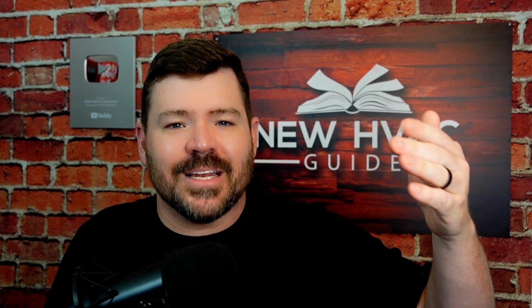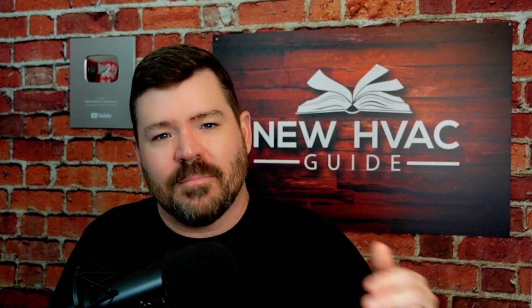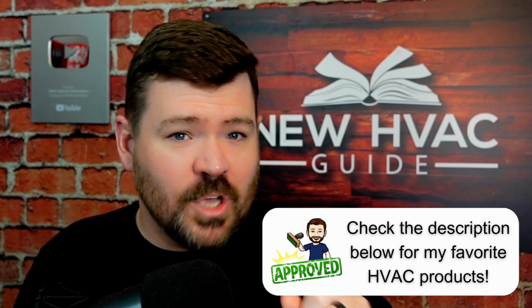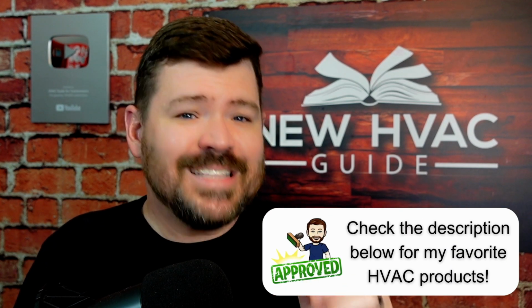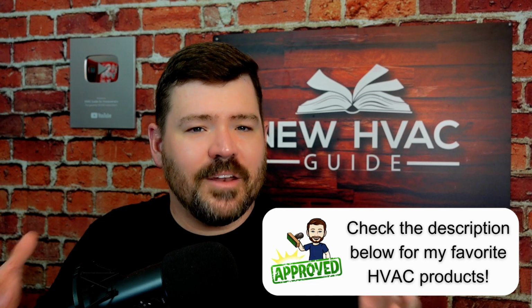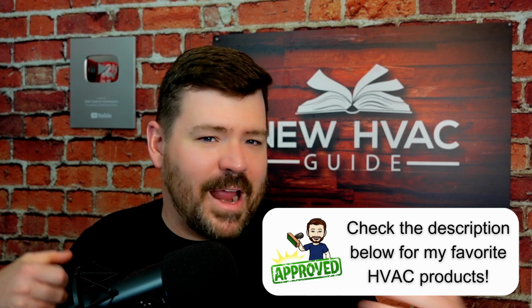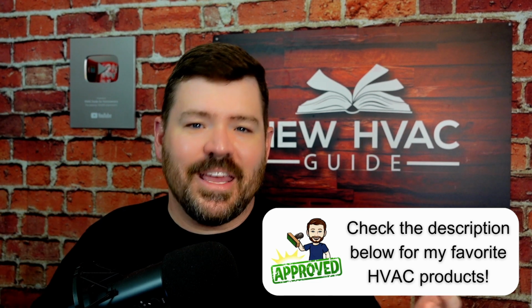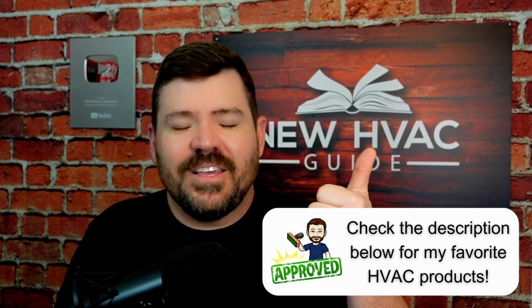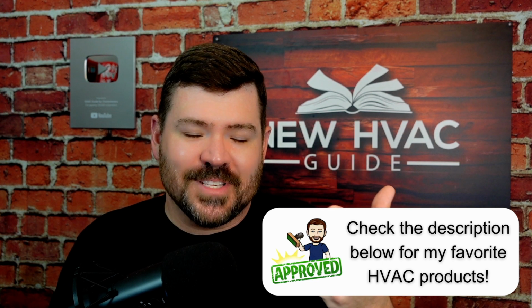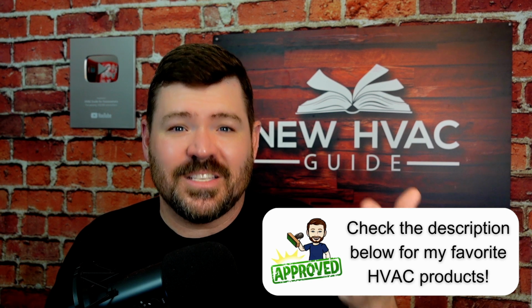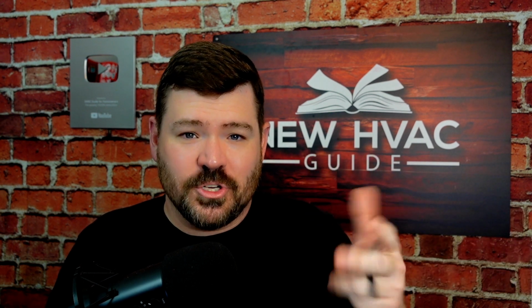Because of that, a lot of guys will intentionally oversize these systems. They'll say, well, let's have the extra capacity because this system can ramp down. And that's a huge problem. We'll talk about why in just a moment, but that's a huge problem. They automatically think that because this system can ramp down, it can alleviate humidity issues. It can alleviate capacity issues if the system was oversized for that space, and it can alleviate ductwork issues because that system can ramp down. That's not how it works.